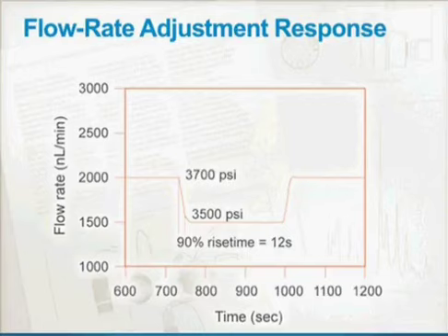So do we talk about percentages, precision at that low flow? That's a pretty tall order, getting down to the 10 nanoliters per minute range and having it be really stable. All those effects are noise on your system. I would say the reproducibility is extremely, extremely high. That's how I would describe it, because you could be at 15 plus or minus 1, but it's exactly plus or minus 1 every day, and that variation averaged out over the course of half an hour or 20 minutes. So it kind of worked out. If you were ever trying to commit that I can give you 15 nanoliters a minute, plus or minus 0.1%, you're on crack. You're only averaging that. That's right. At any moment in time, that's not exactly it. So that's sort of the issue with that.